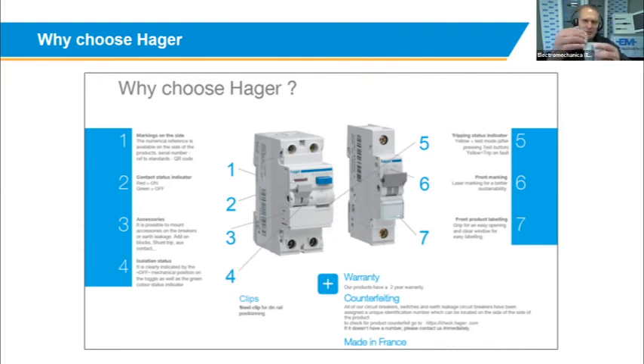So instead of loosening all your bus bars on top to take this product out, because normally that's what you need to do, you need to remove everything on top so you can clip this product out of the installation and take it out. But what they've done is, with the 2 clips in this instance, you can actually unclip it on the top and at the bottom, okay? And you clip it out and you can slide it out of your product without needing to loosen all your bus bars and cables on top of the product. So behind the scenes, there's a lot of other features that, as I said, are not always mentioned.